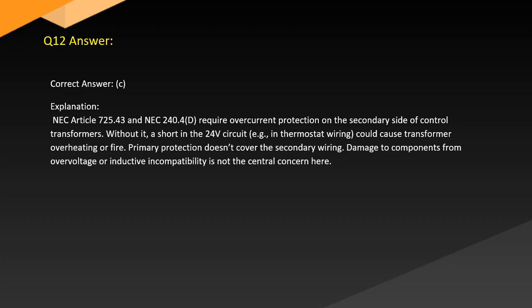Without it, a short in the 24-volt circuit, e.g. in thermostat wiring, could cause transformer overheating or fire. Primary protection doesn't cover the secondary wiring. Damage to components from overvoltage or incompatibility is not the central concern here.